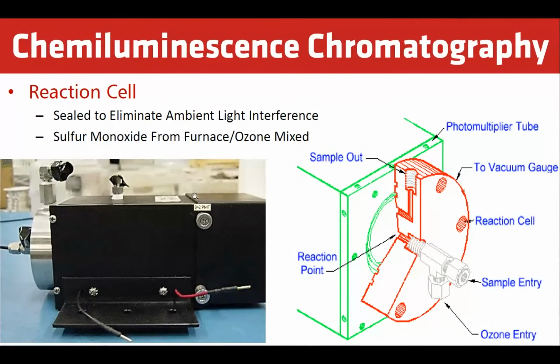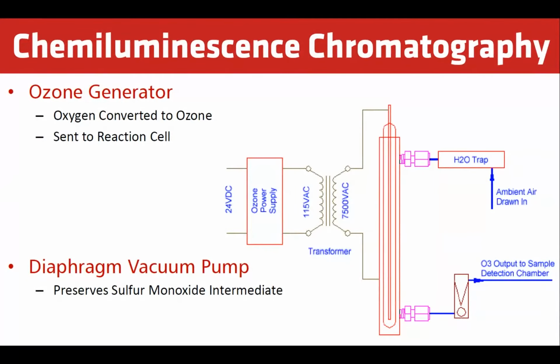SO enters into the photomultiplier or the sample cell there. We add ozone to produce SO2, which then creates a light source. And the light source is picked up by the photomultiplier tube, giving us a signal proportional to the concentration of the sulfur. Part of the chemiluminescence reaction, this requires ozone. So we have our own ozone generator. We take oxygen, convert it to ozone, and send it to the reaction cell.